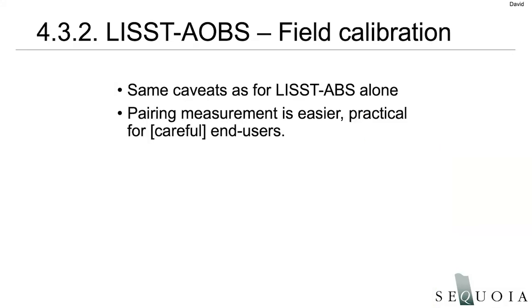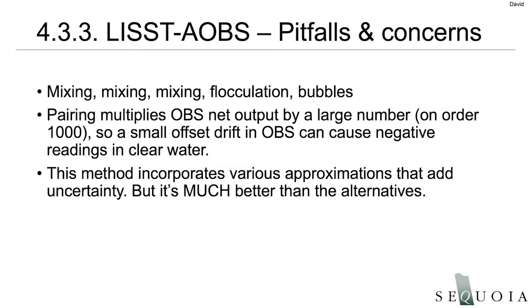Pretty much the same considerations and precautions go into this as into the ABS calibration. In a lot of ways, this is an easier thing for most users. It doesn't require quite as much fiddling around, quite as much optimization and careful measurement as the basic particle calibration of the ABS does. So it is something that we tell users, yes, you can probably do this as long as you're careful in the lab and use the right particles. Same considerations, mixing, but as I keep saying, it is noticeably easier for these smaller particles than it is for the 75 to 90.